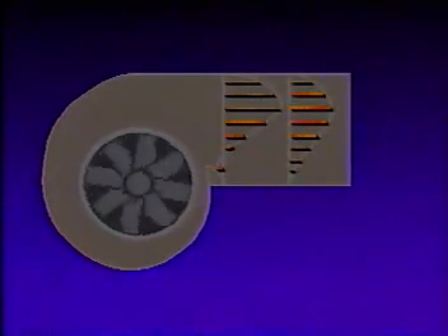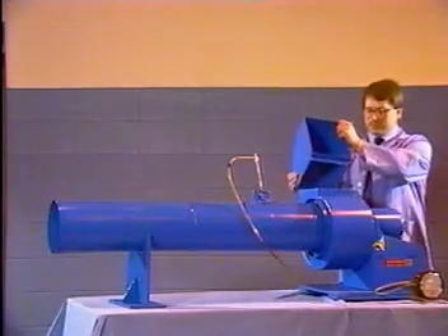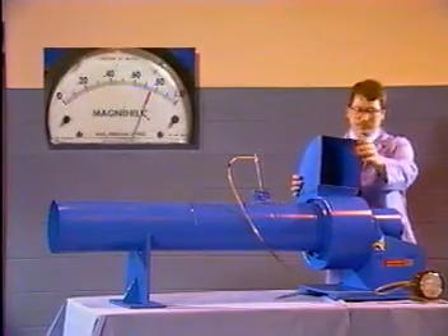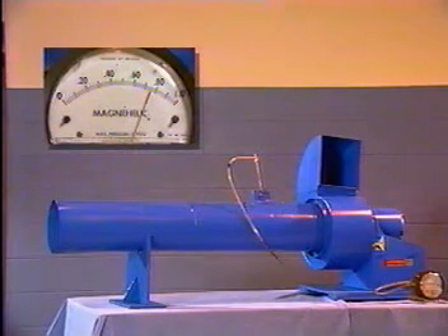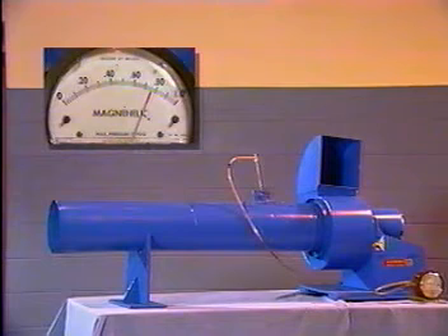The air, which has weight, is thrown to the outside of the scroll. Air requires several duct diameters for its velocity profile to even out. That's why outlet ductwork is so important. The use of elbows at the fan outlet should be avoided, but if you must use an elbow outlet, make sure the turn in the elbow follows the same direction as the fan wheel rotation.